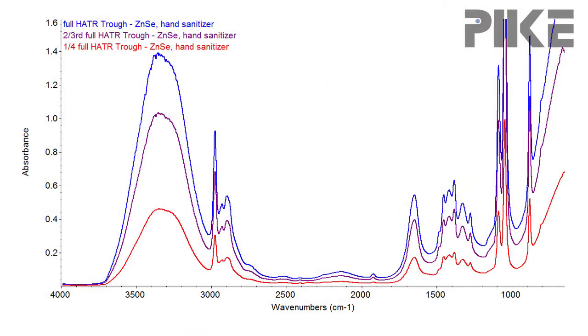You can see from the spectra that depending on how much surface area I covered of the crystal, the strength of the absorbance bands changes. So just to recap: when doing quantitative analysis, cover the surface area completely with your sample. Thanks for joining us and we'll see you next time.